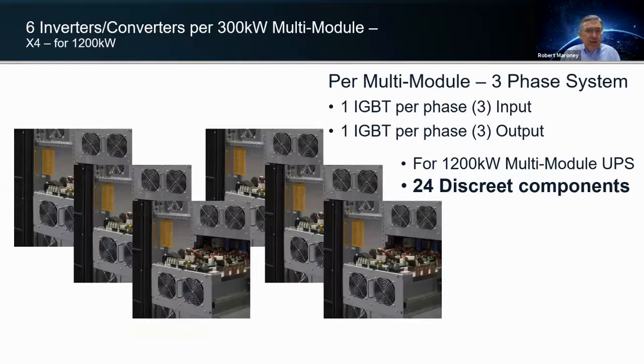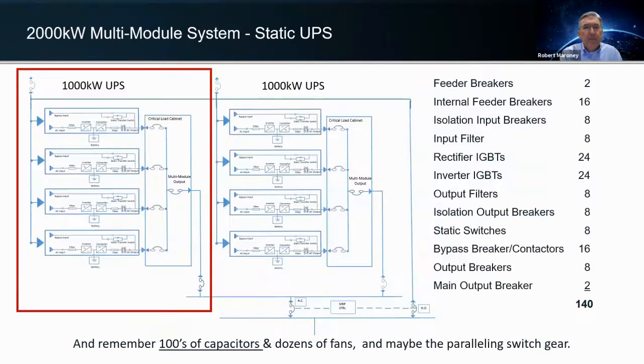You have IGBTs to do your power electronics. Each 300 kilowatt system is going to have 3 input IGBTs and 3 output IGBTs for each of the 3 phases. Now you're getting up to as many as 24 discrete components inside of that UPS. In a 1,000 kilowatt system, you're looking at almost 70 components, when you look at internal breakers, isolation breakers, filters, IGBTs, output filters, static switches, bypass contactors. It all adds up. As I said, in a 2,000 kilowatt system, you'd be looking at a count of over 140 components, not including the capacitors and fans that we just talked about.